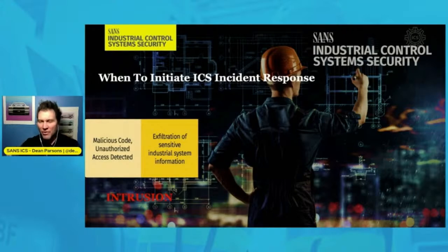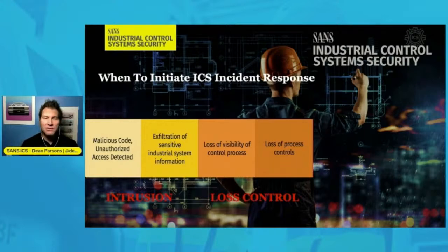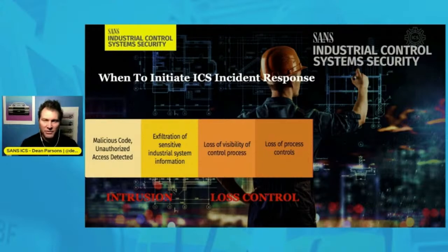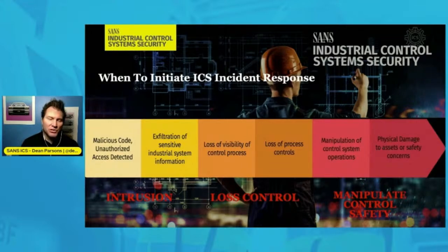Beyond this, using those four methodologies for threat detection, you can detect the adversary in an area where they're going to be potentially causing loss of control of the environment — so the loss of visibility to control the process, or loss of process control itself. We're progressing from an initial intrusion to a more damaging condition: potential loss of control system ability. Beyond that, what we're most concerned about is the adversary in the later part of an attack — the manipulation of the control environment, potentially manipulation of safety instrumented systems, potentially causing physical damage inside the environment.